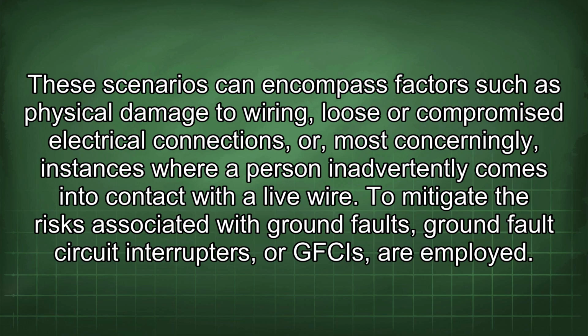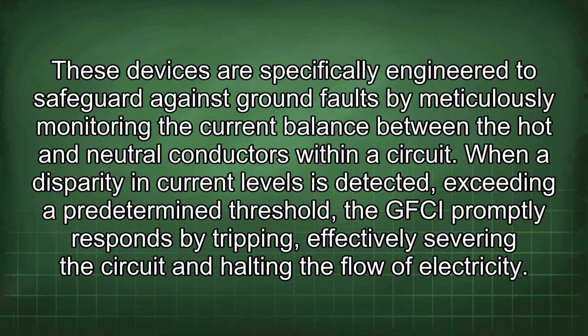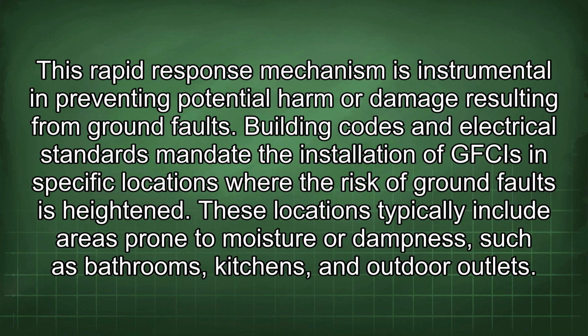To mitigate the risks associated with ground faults, ground fault circuit interrupters, or GFCIs, are employed. These devices are specifically engineered to safeguard against ground faults by meticulously monitoring the current balance between the hot and neutral conductors within a circuit. When a disparity in current levels is detected, exceeding a predetermined threshold, the GFCI promptly responds by tripping, effectively severing the circuit and halting the flow of electricity. This rapid response mechanism is instrumental in preventing potential harm or damage resulting from ground faults.